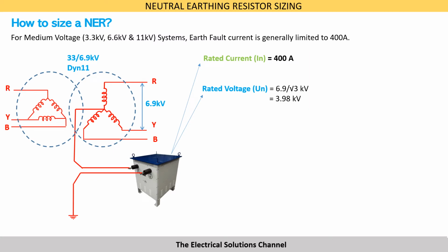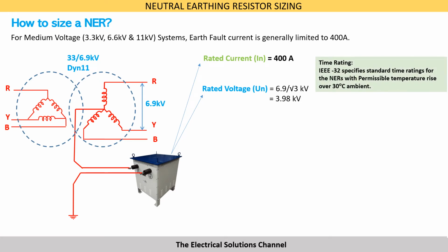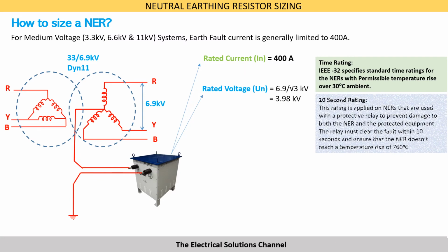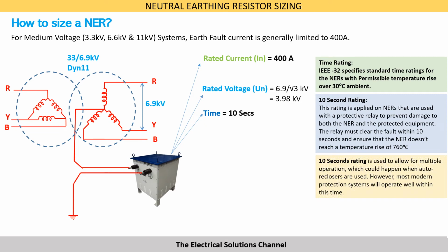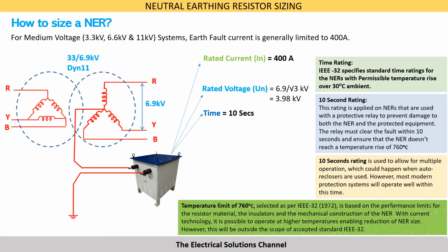For the time rating of an NER, IEEE 32 specifies standard time ratings with permissible temperature rise over 30 degrees C ambient. The 10-second rating is applied on NERs that are used with protective relay to prevent damage to the NER and the protected equipment. The relay must clear the fault within 10 seconds and ensure that the NER doesn't reach a temperature rise of 760 degrees C. The 10-second rating is used to allow for multiple operations, which could happen when auto reclosers are used. However, most modern protection systems will operate within this time.